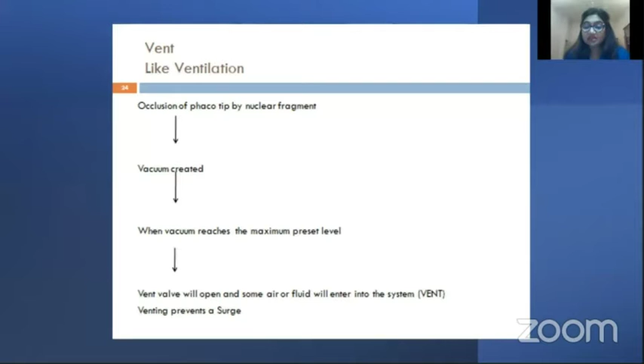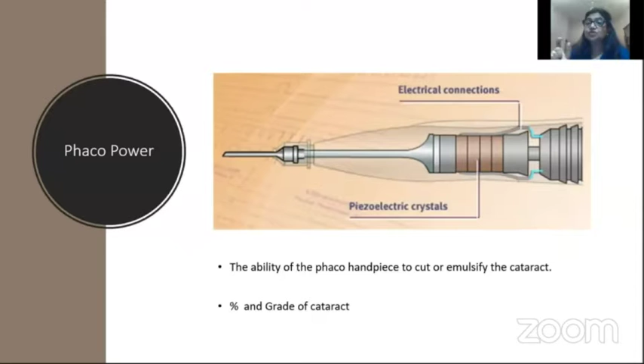Now, phaco power is the ability of the phaco handpiece to cut or emulsify the cataract. It has piezoelectric crystals which are excited by electrical connections. And this electrical energy is converted into mechanical energy whereby the tip begins to move or oscillate. It is measured in terms of percentage. That means if it is a softer cataract, you can keep the phaco power less, to about 20 or 30 or 40%, whereas if it is a harder cataract, you can even go up to 80 or 100%.